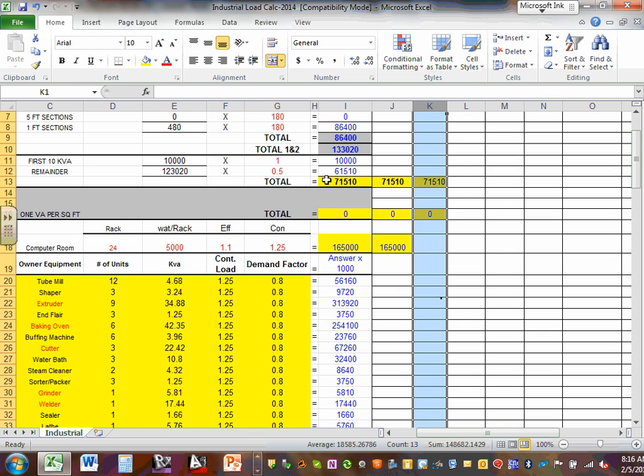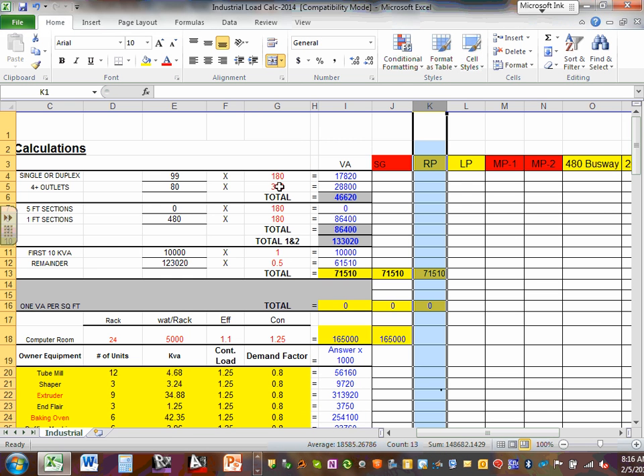Do you guys remember the 7? Here's a calculation that we have just done. 180, all the calculation, derate by the first 10. Do you guys remember that? And you came up with this number. This is an already derated number. Did you guys hear me? Here's the 180 times the number of receptacles. If you're using quads, 80 times the number of quads.